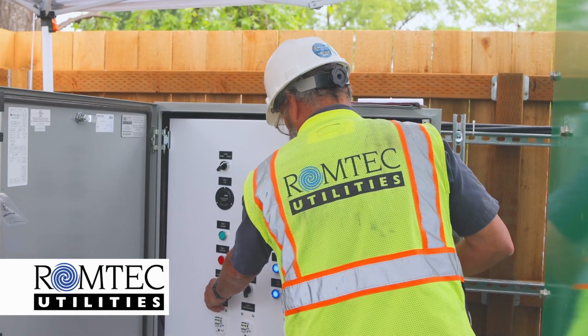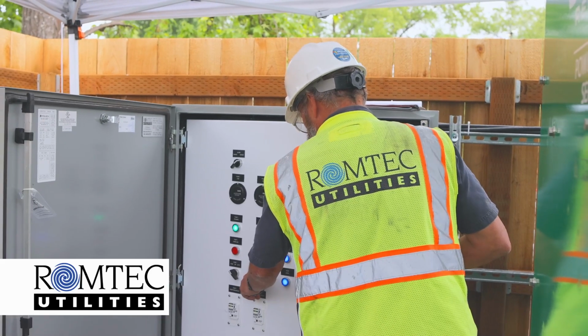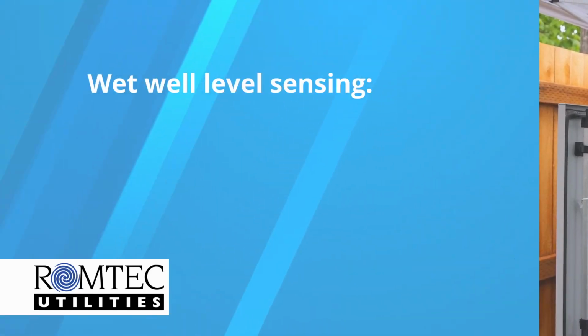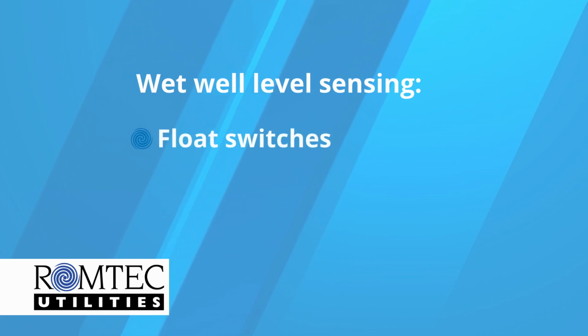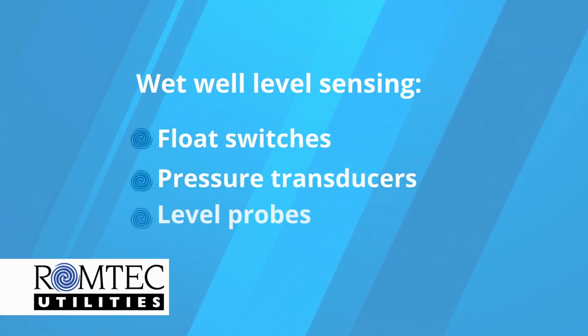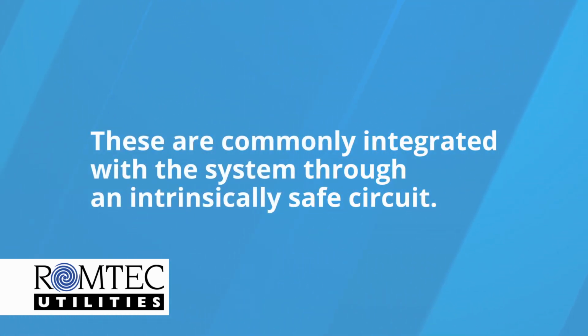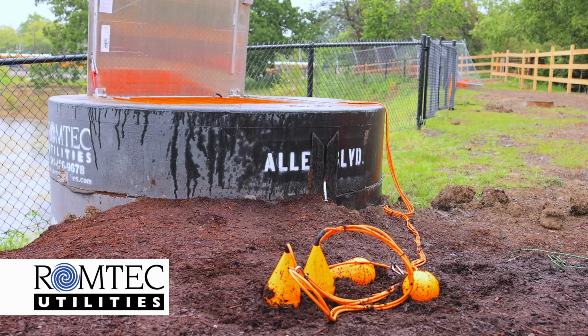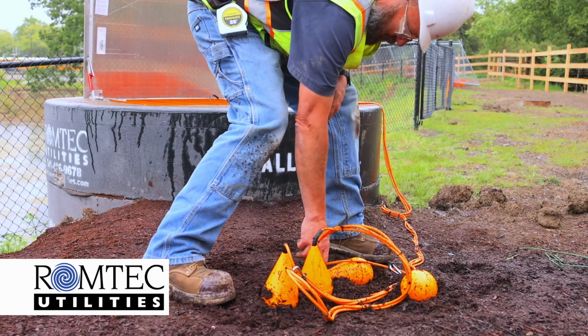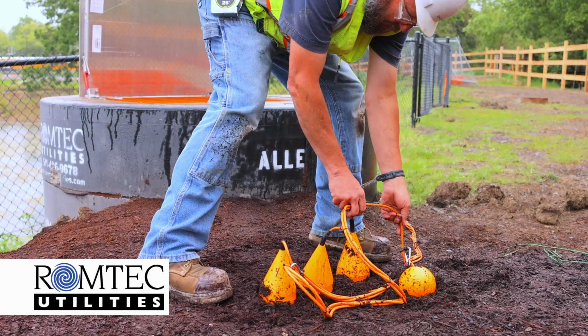One aspect of ensuring safety is through the implementation of intrinsically safe circuits. Wet well level sensing, whether float switches, pressure transducers, or level probes, is commonly integrated with the system through an intrinsically safe circuit. Liquid level sensing devices are typically installed in the classified area of a system.